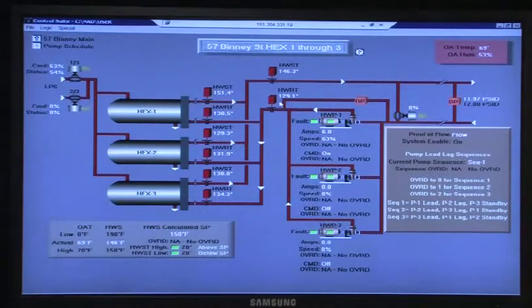It goes through. Then you've got return temperature here. It exchanges. You've got hot water supply out. Where's your set points down here? Down there, you calculate it as 150 based on the outside air reset, and then you're at 146 up there. And as far as your alarm set points on this, if something looks a little strange on the bottom, it says hot water high 20, low 20, above set point, below set point.